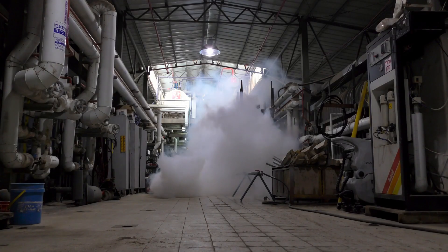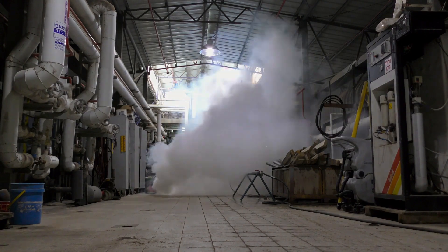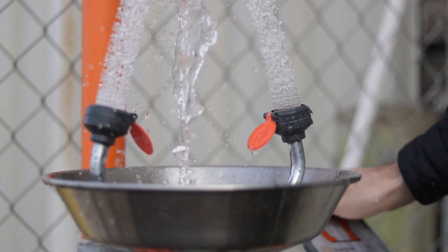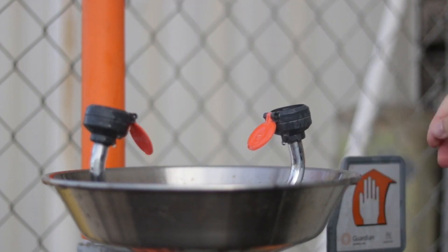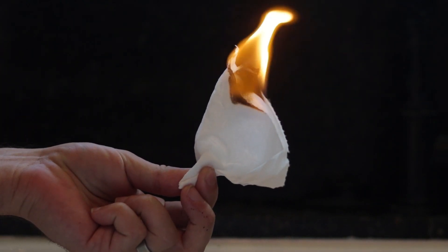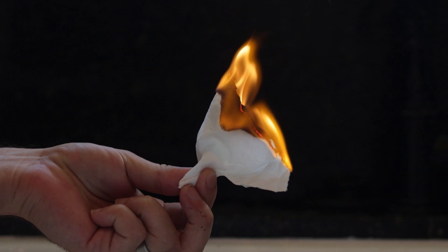One should be warned, however, that while ammonia will eventually rise due to its vapor density, large releases have been known to stay at ground level temporarily. The ability of a substance to dissolve in water is referred to as its solubility. Ammonia is highly soluble, which means it readily absorbs into water. This explains why eyewash and safety showers are essential for decontamination after exposure occurs. In addition, some refrigeration systems utilize ammonia diffusion tanks as a means of neutralizing ammonia released through a pressure relief valve. While flammability is generally not the primary concern, it is important to know that ammonia vapor may burn in air concentrations between 15 and 28%.